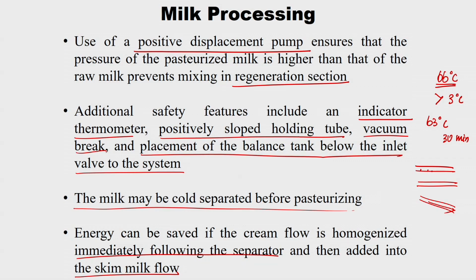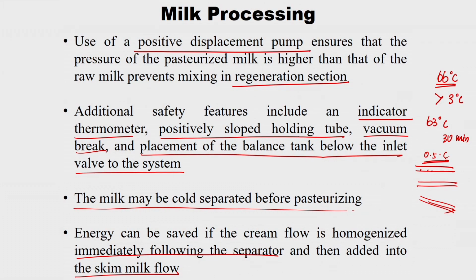We also need to ensure all the valves, inlet tube, outlet tube, everywhere, there should not be any delta T, in the sense if it has to be maintained at 63, all the equipment should also be at the same temperature. If at all there is a delta T, it should be less than 0.5 degree centigrade. Literally there should not be any temperature difference — if at all, only 0.5 degree centigrade is allowed. So these are all the safety measures we need to ensure.